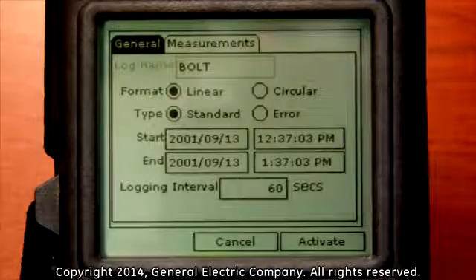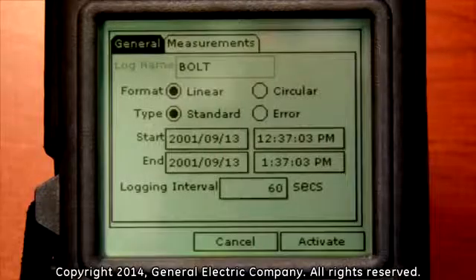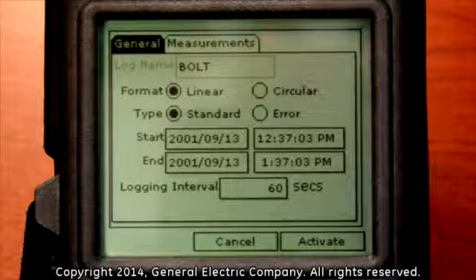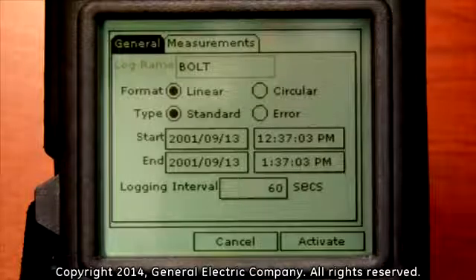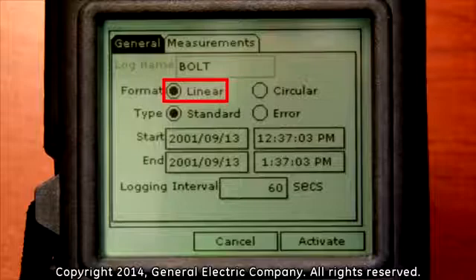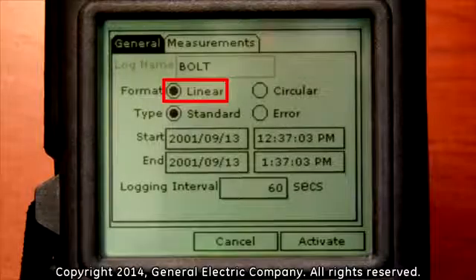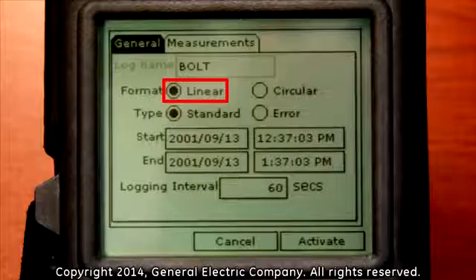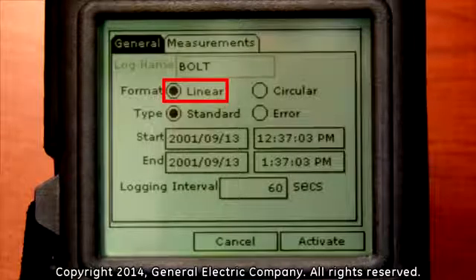This will take you back to the general tab, which will be highlighted at the top of the display screen. Under the general tab you will need to choose which type of log format you will use. A linear log is for starting and stopping data logging, taking measurement recordings at specific times and specific intervals. This format is a discrete logging program function.